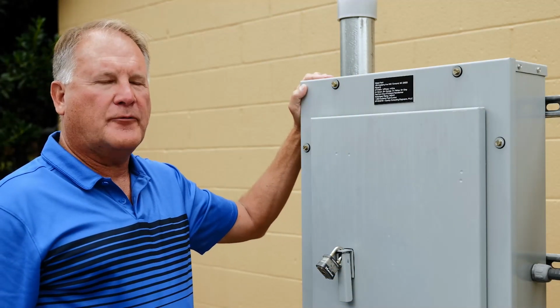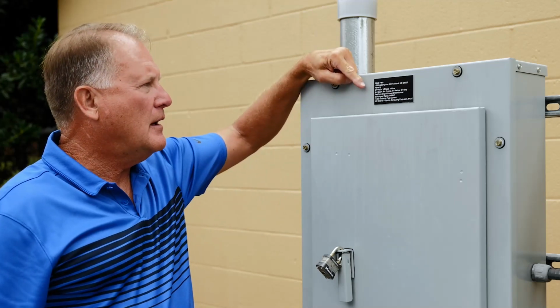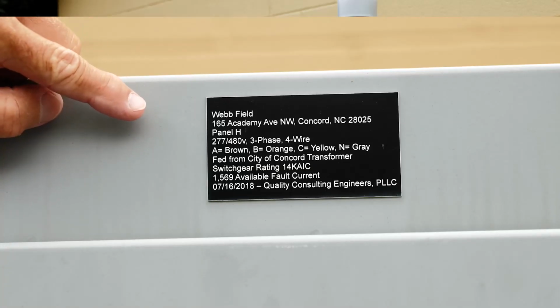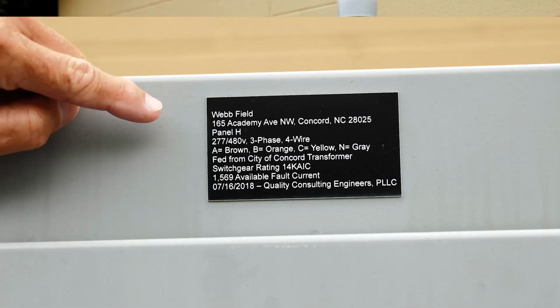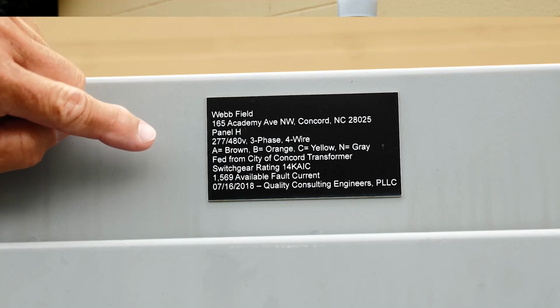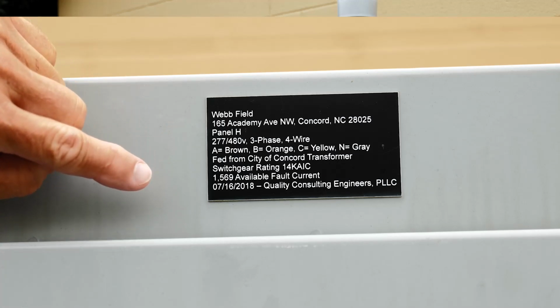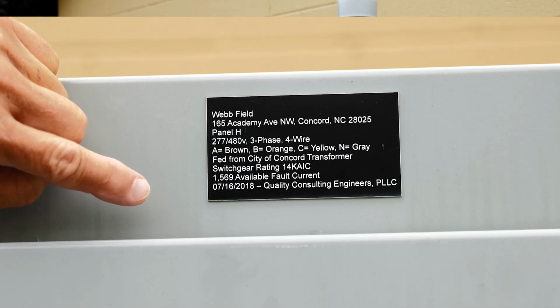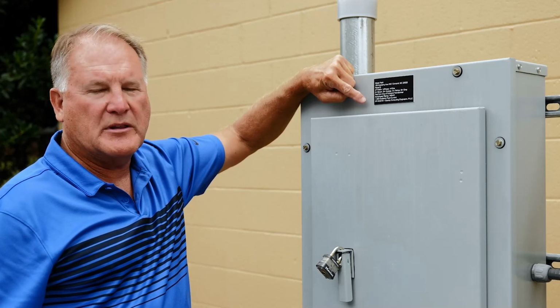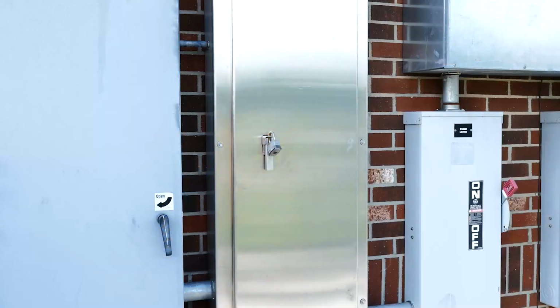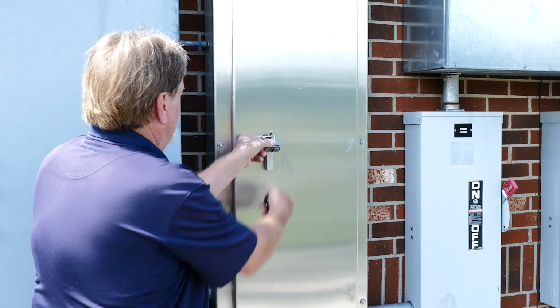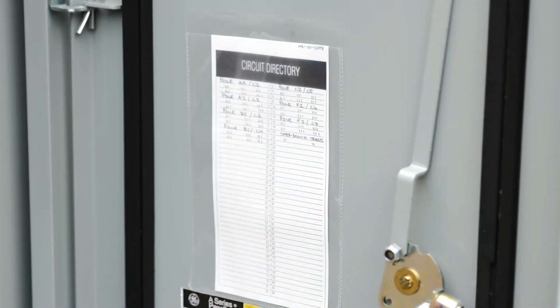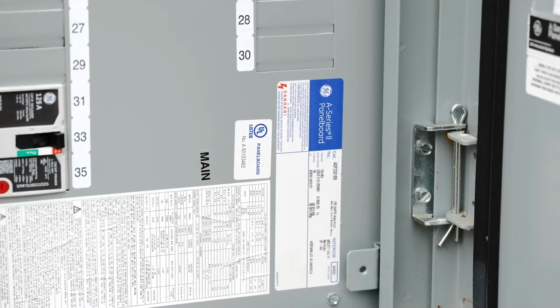This is an example of proper external panel labeling. It should include the name of the project, the address of the project, the panel name, the voltage and phase, the wire coloring, where this panel is fed from, the AIC rating of the panel, the available AIC rating, and who determined the AIC rating, whether it be the power company or an electrical engineer. This panel has its cover in place, all screws are intact, a lock to prevent it from being accessed from unauthorized personnel, circuit directory, safety labeling, including arc flash.